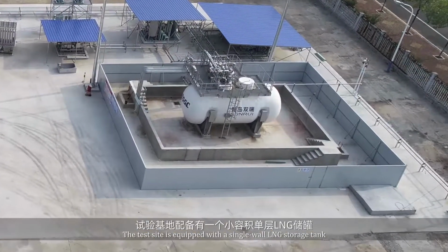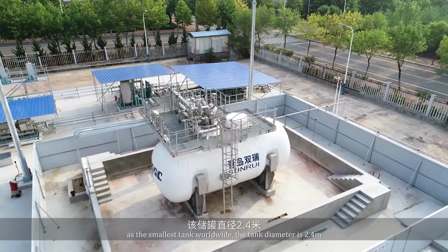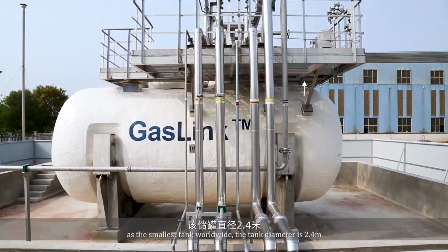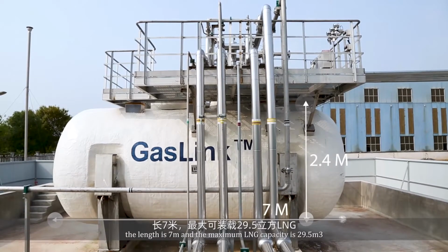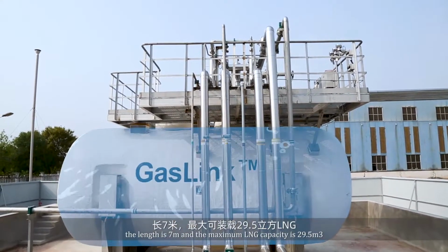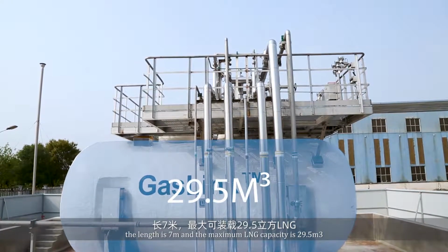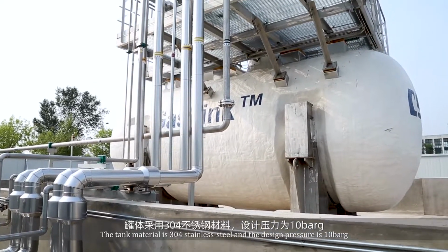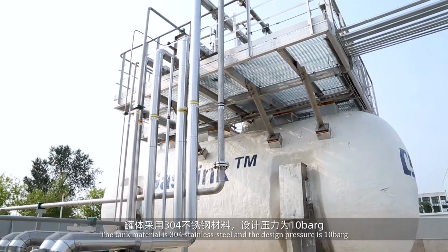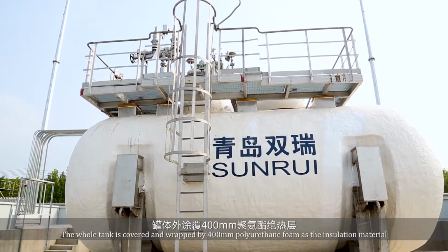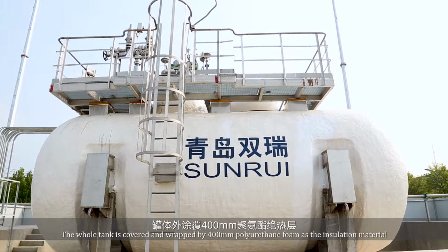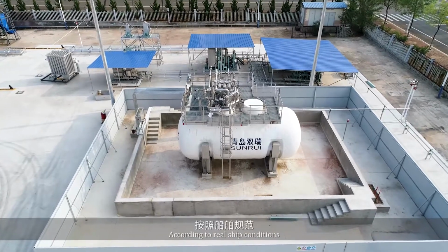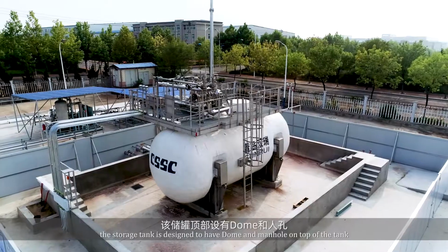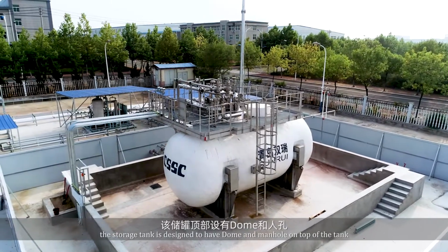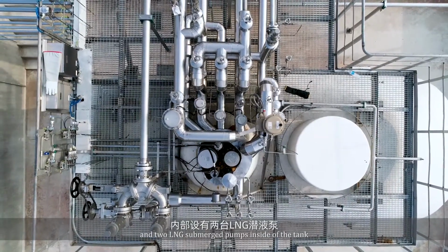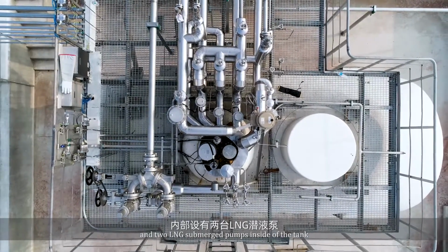The test site is equipped with a single-wall LNG storage tank, the smallest tank worldwide. The tank diameter is 2.4 meters, the length is 7 meters, and the maximum LNG capacity is 29.5 cubic meters. The tank material is 304 stainless steel, and the design pressure is 10 bar. The whole tank is wrapped by 400 mm polyurethane foam as the insulation material, according to the real ship conditions. The storage tank is designed to have a dome and a manhole on top of the tank, and two LNG submerged pumps inside the tank.